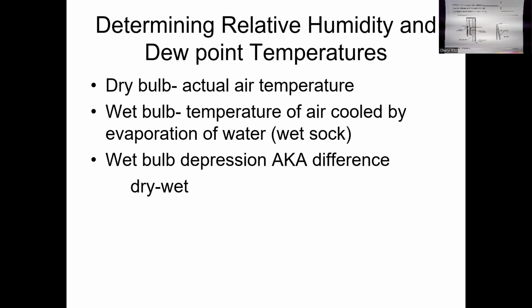Wait, what if you put the sock in warm water? Immediately the temperature would rise, but when you spin it, it would still evaporate, it would still get colder. What if you make it really cold? Same thing, initially it will drop, but when you spin it, it won't be that cold, because it'll then just get the temperature after evaporation. So that's why we don't just spin this for 2 seconds, you spin it for 2 to 3 minutes. It is a lot of time, it's not a quick process. Not that difficult, though.